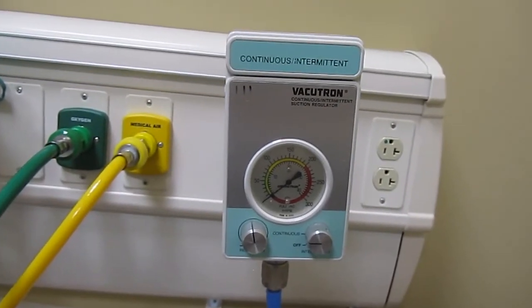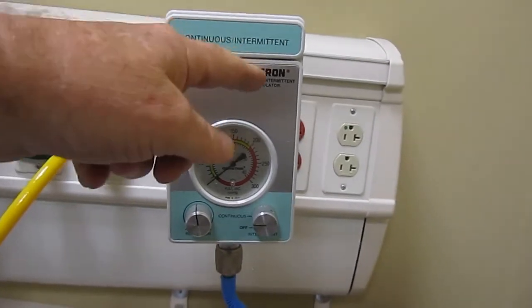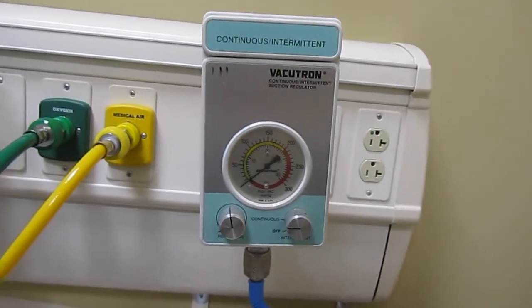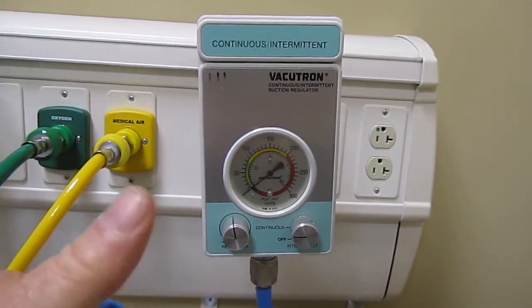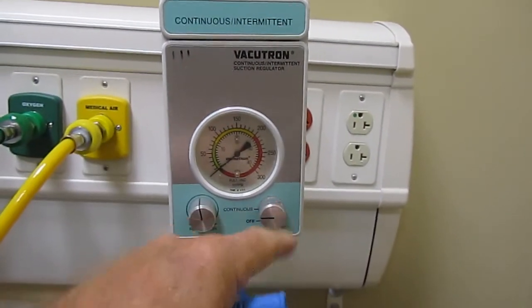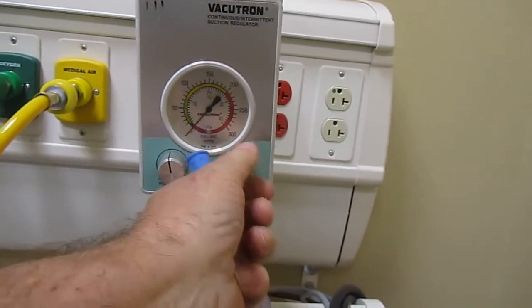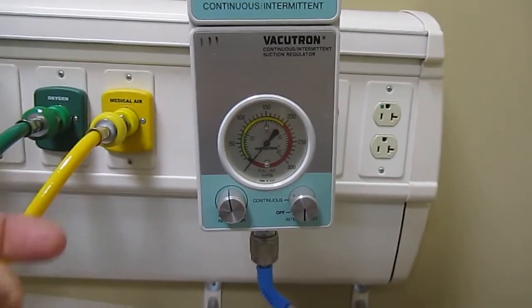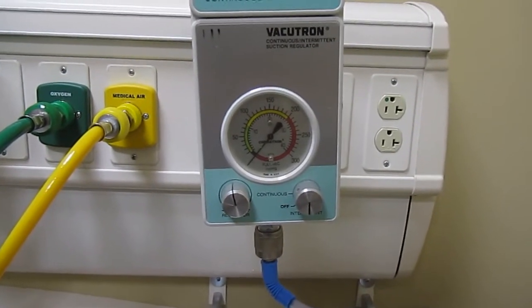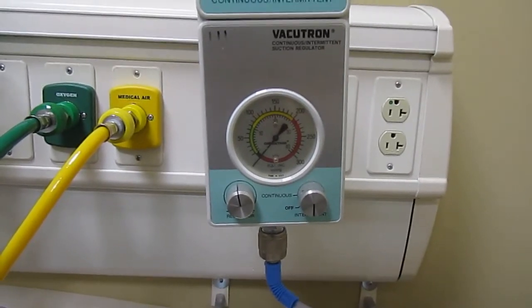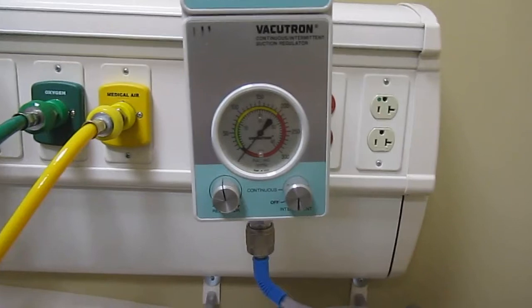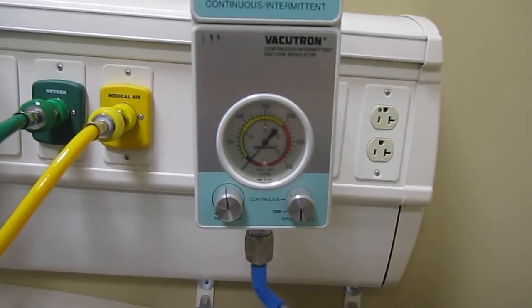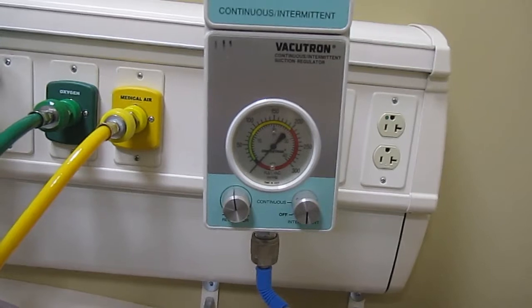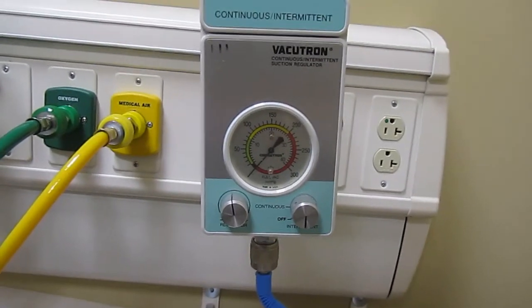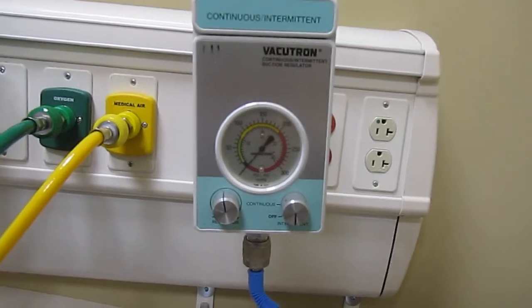The suction regulator. This is continuous and intermittent. On continuous, the suction is always on. On intermittent, it only comes on every now and then. It will turn on and apply suction, and then it will turn off. And this is more for GI tract suction, where they don't want the suction tube to be sticking to the wall and causing GI bleeds.